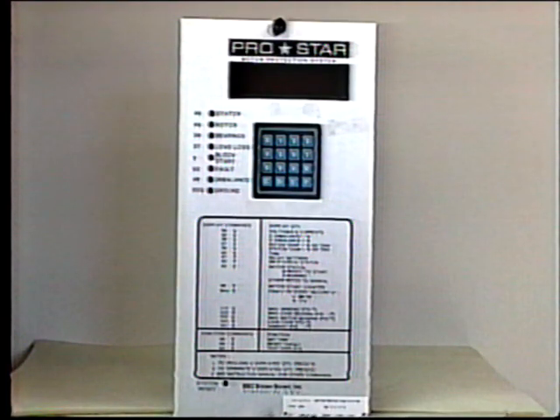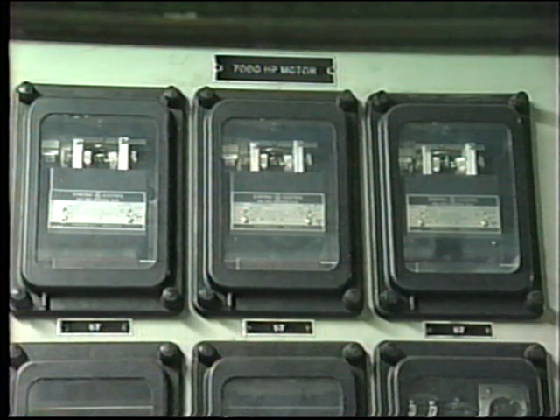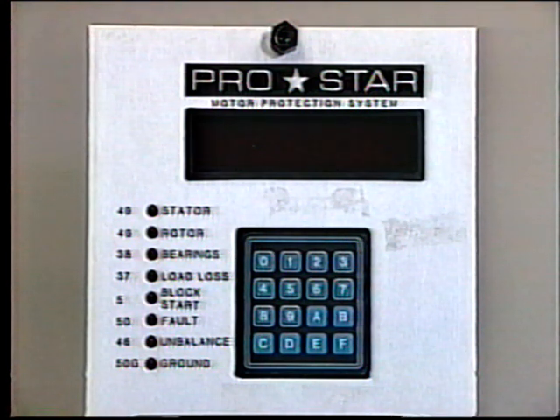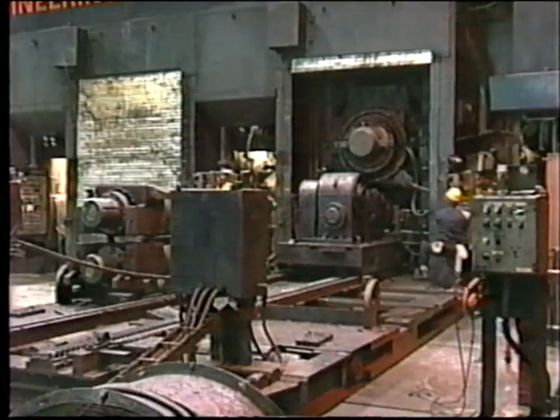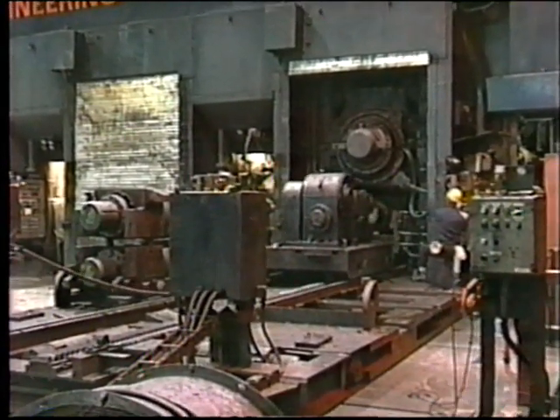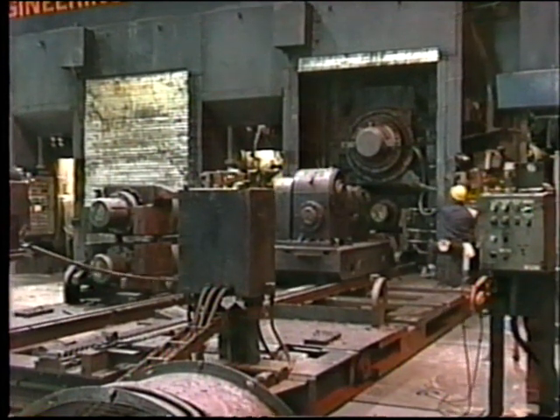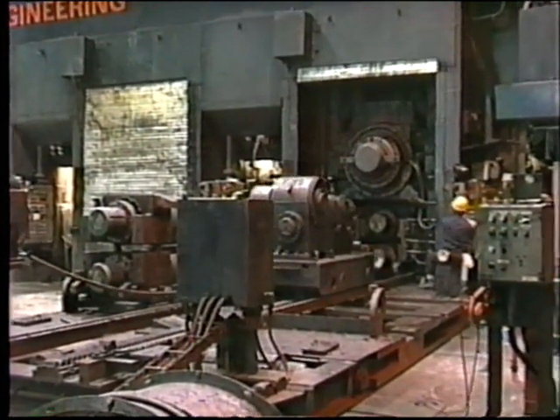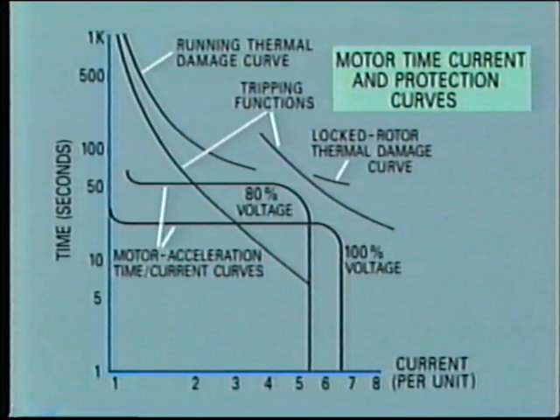Microprocessor relays are quite widely used in industrial plants for protection of large motors. In this particular application, it shows several clear advantages over the electromechanical type. For example, various protective functions are combined in one unit. Also, it is robust and less susceptible to misoperation due to vibration and dusty atmosphere, which often exist in industrial locations. Moreover, it is able to overcome some of the particular problems associated with motor protection and the resultant compromises that have to be made in setting up an electromechanical relay. You'll remember that we discussed this in an earlier tape.